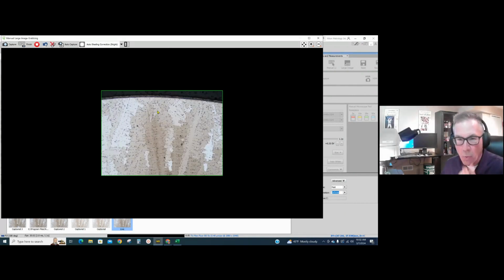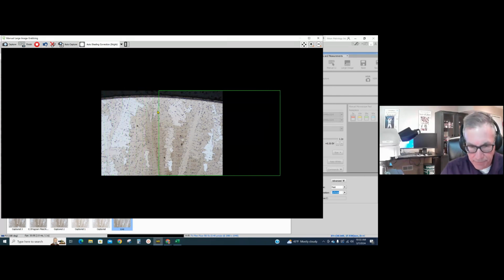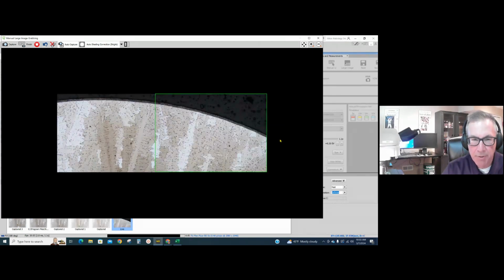This is a situation where you don't want to be on auto expose because you don't want these images to be different brightnesses. You can see my live image, and I have a green box around my image. I'm manually moving my stage in the X direction, and you can see that green box move to the right. I'm going to turn my auto capture on because this works pretty good. As I keep moving my stage, that green box is very close to turning pink. When it turns pink, I'm going to stop, and you can see it automatically added the next frame.